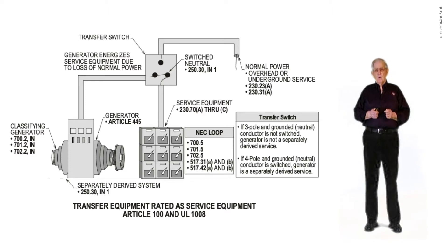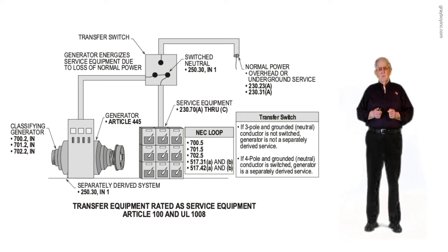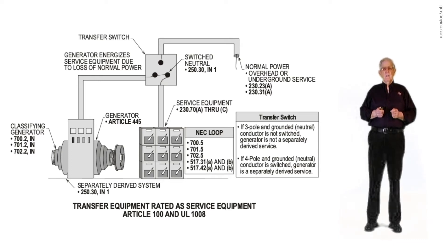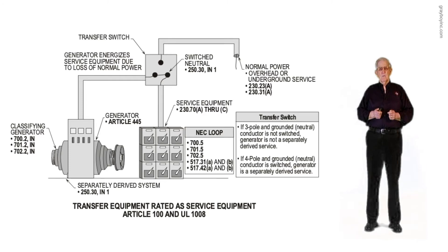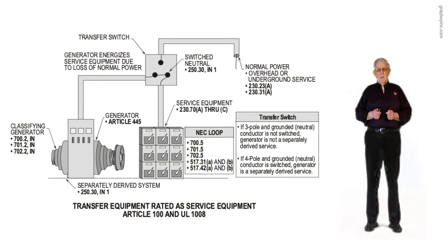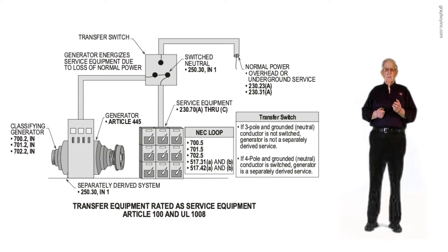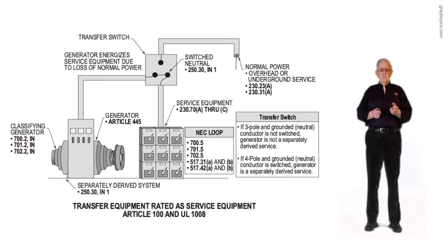If it happened to be classified a 701 generator, you could mix the wiring with the normal power, and you could do the very same if it was classified a 702 generator, which is an optional standby generator. With an optional standby generator, you can bring it on manually or automatically and design it to supply the loads that the user wishes to supply.